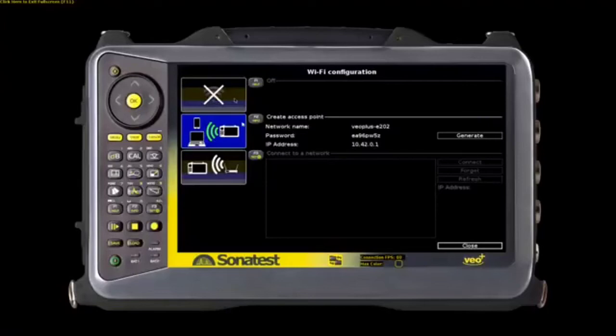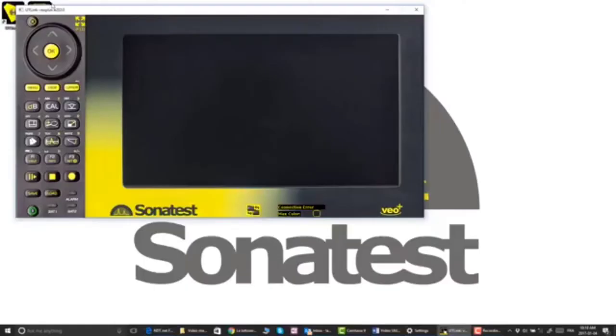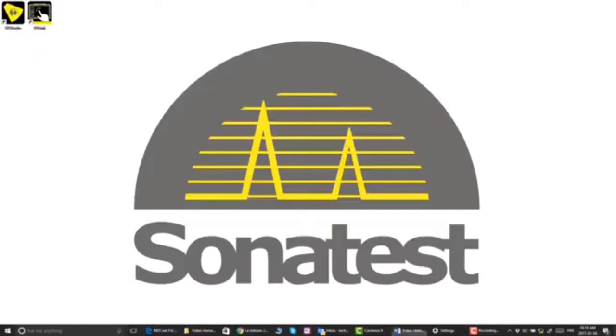As you can see, after turning the signal off, the connection between our devices has been broken and the connection status is lost. In this situation, to control your VEO Plus remotely, you must connect via an Ethernet cable. I'm now replacing the connection to the network to the one directly in my computer. The device should again be connected, but I still need a valid IP address to use the UT-Link and the VEO Plus.